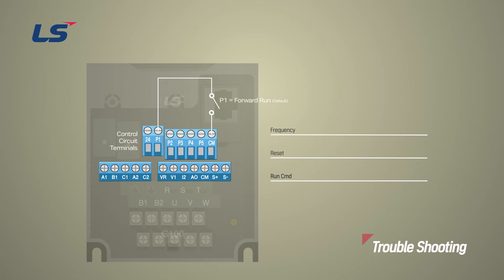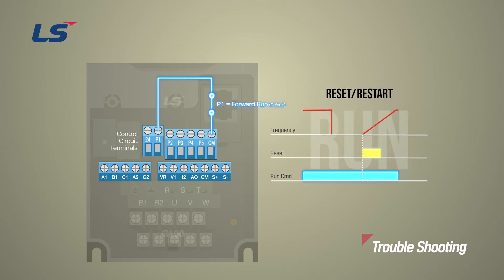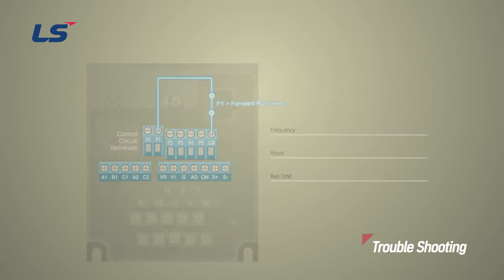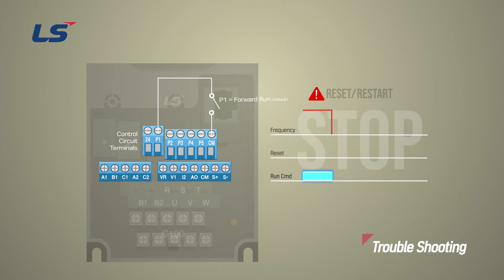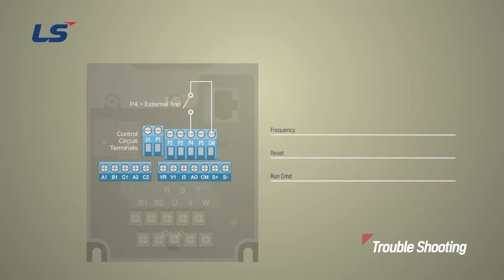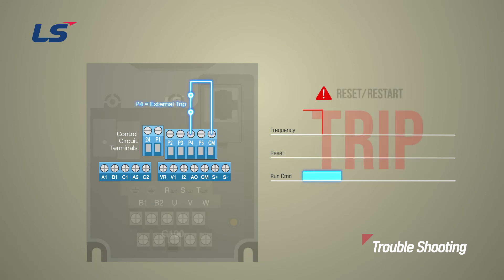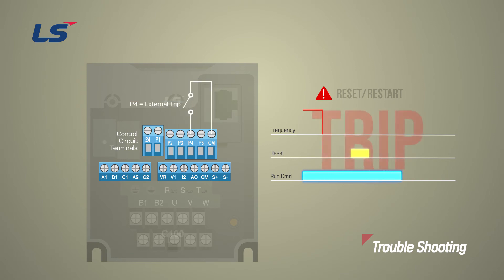The following is a list of things to check when the automatic restart function does not work properly. First, the Reset-Restart function operates only when the command source of the terminal block is on. If the terminal block command source is turned off, the function does not work, so be sure to check if the command source is on. Also, if the P4 terminal set as external trip is on, the trip status continues and restart is not possible. Therefore, it must be opened after generating an external trip.